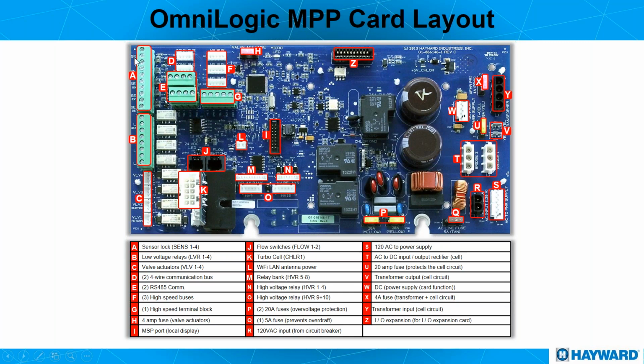On the letter A, that's going to be my sensors. We have connection here for up to 4 sensors. On gas heaters or heat pumps, we have connection for 4 heaters. And then we have these bars right here with the letter E that we'll use for connection for data, data like variable speed pumps.